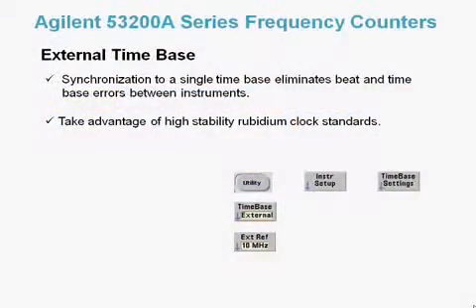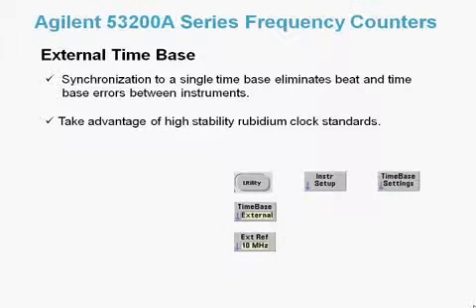To summarize, using an external time base allows synchronization to a single time base, which eliminates beat and time base errors between instruments. It also enables you to take advantage of the many high-stability rubidium clocks that are available on the market.